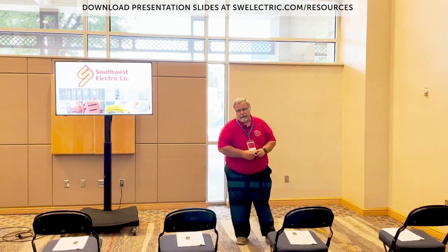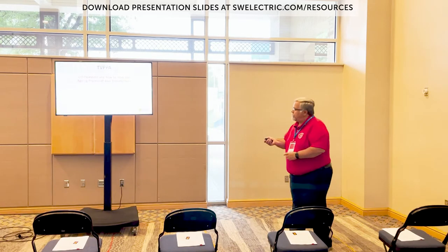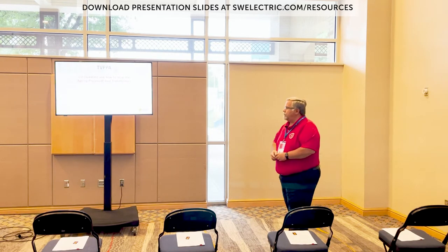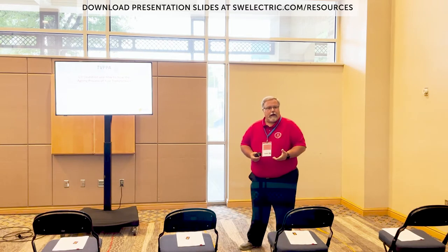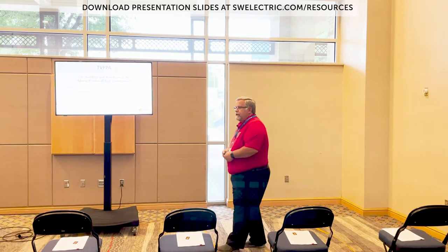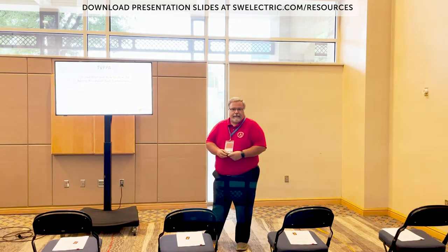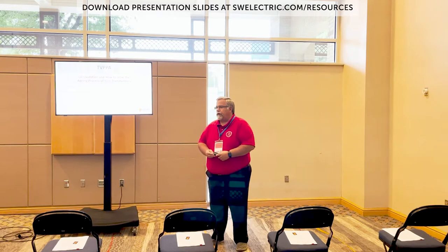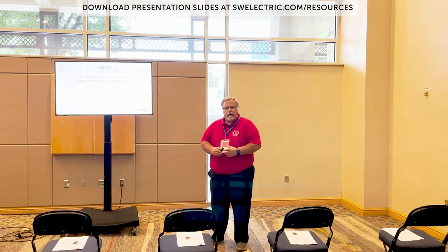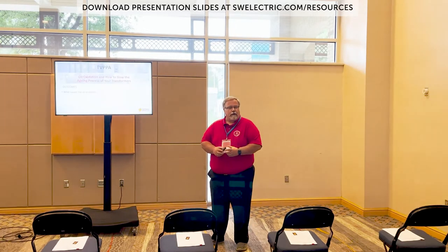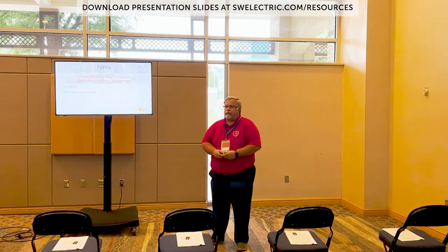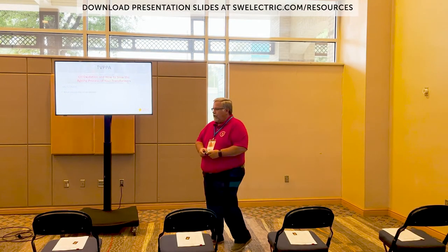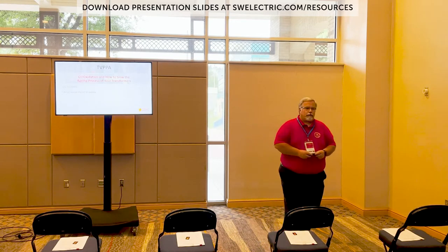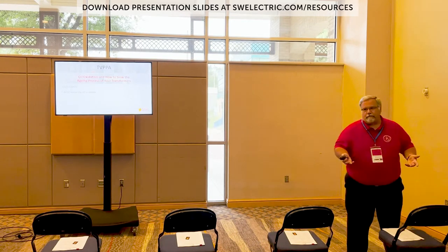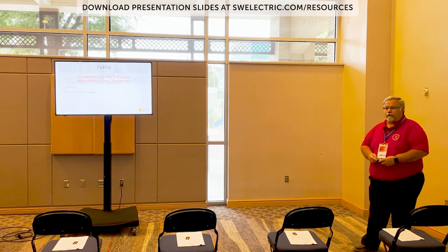So there's three things we really want to take care of on the transformer. With this in mind, what I want you to really take away from this is what causes the oil in the transformer to oxidize. That oil was put in the transformer for a reason. Back in the late 1880s, there was a chemist that was brought into the electrical industry, and he was brought in to just figure out what we could do to disperse the heat from the winding of the transformer. And he actually looked at vegetable oil, corn oil. Well, what can we get today? Vegetable oil, FR3, for our transformers.